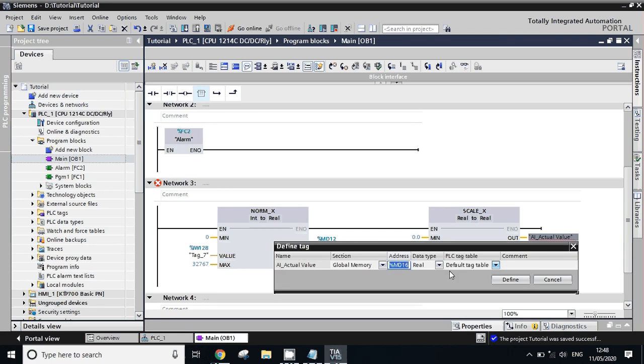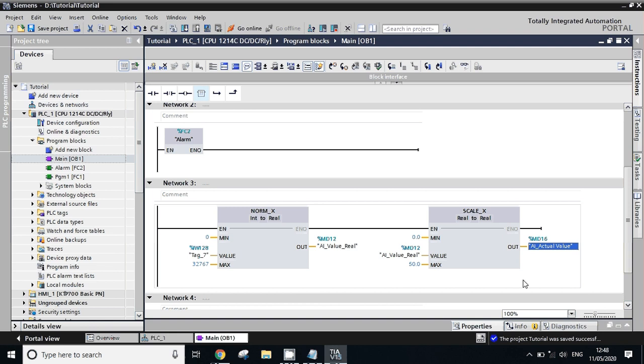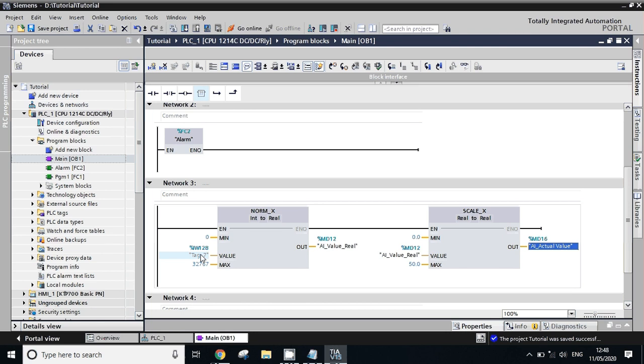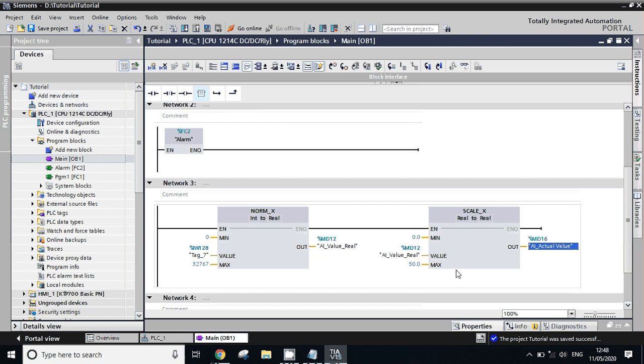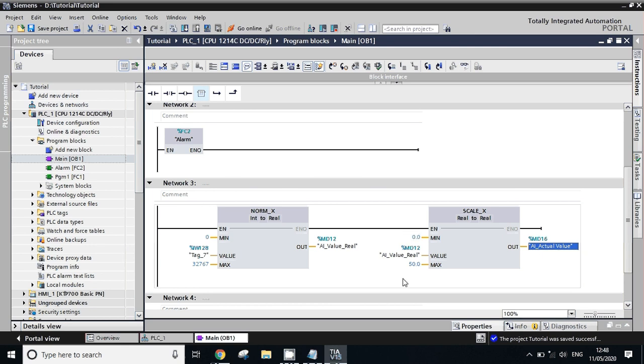Define the tag. It will take the next address automatically. So what happened here? The input range is from 0 to 32,767. This analog input transmitter gives us the value between 0 to 32,767. It converts into real. It normalizes this value and we show it between 0 to 50. The scale is between 0 to 50, so that's why our actual value is between 0 to 50 based on the input value of 0 to 32,767. So just we will run the program.